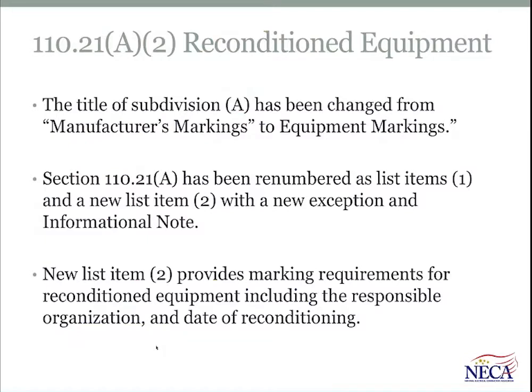Something else that's new in the NEC that is probably long overdue, if I can interject an opinion on it, it's not related to anything new that's going on in the industry. It actually relates to ongoing practices of refurbishing, remanufacturing, or reconditioning electrical equipment and then putting it back into service. So 110.21 was restructured into a subdivision with a list item 1 that contains all of the manufacturer's marking requirements that were previously there, but a new list item 2 was added and a new exception, an informational note. And this new list item 2 provides marking requirements for reconditioned equipment, including the responsible organization and the date of the reconditioning. So in other words, there's some more traceability, if you will, and there's some more responsibility for those organizations that would be responsible for the reconditioning of equipment that is put back into service.